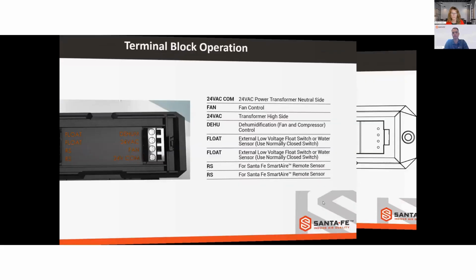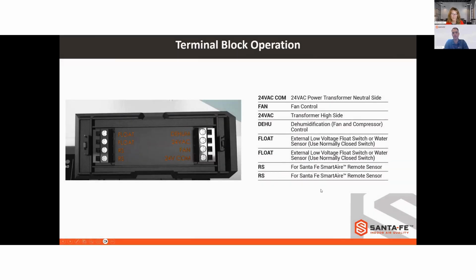And then next we have our terminal block. And you'll see on here that we have a lot of features that sometimes you don't see on other dehumidifiers. Most importantly, that 24-volt AC, where you are able to wire a motorized damper directly to the dehumidifier. We also have floats, so you can wire external float switch directly to the unit. And then we also have what you see there, what you don't commonly see, is RS. And that's for a new Santa Fe SmartAire remote RH sensor that we have launched with these units that we'll talk about as well.